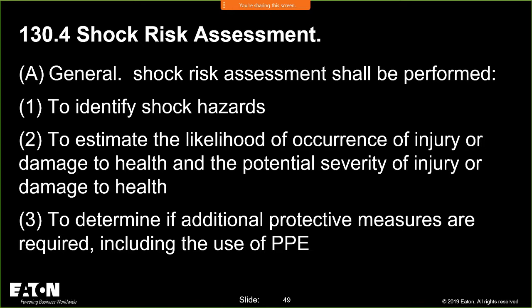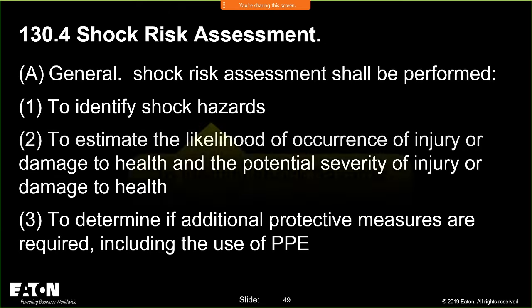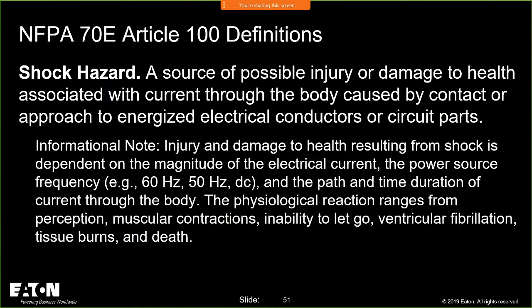So to identify it, we have to understand what is a shock hazard and what isn't a shock hazard. If you look in Article 100, they define a shock hazard as a source of possible injury or damage to health associated with current through the body caused by contact or approach to energized electrical conductors or circuit parts. So if you think about it, if you come in contact with something, current's going to pass through your body.